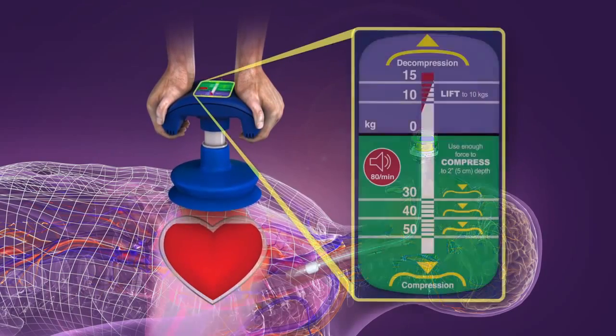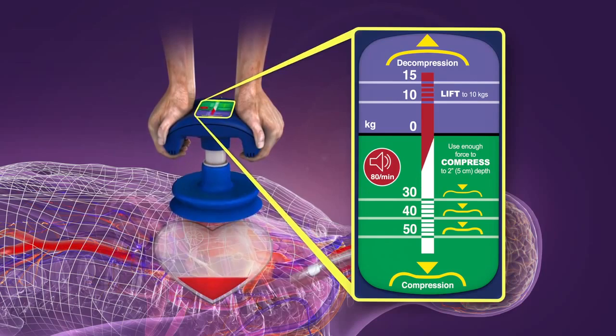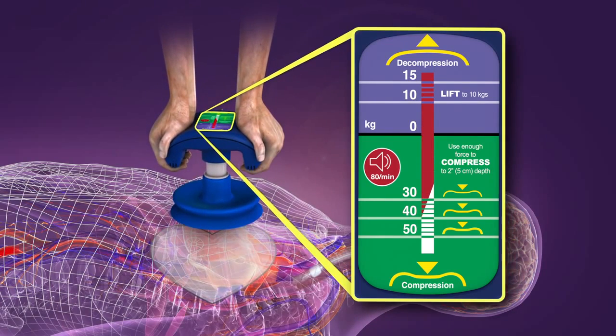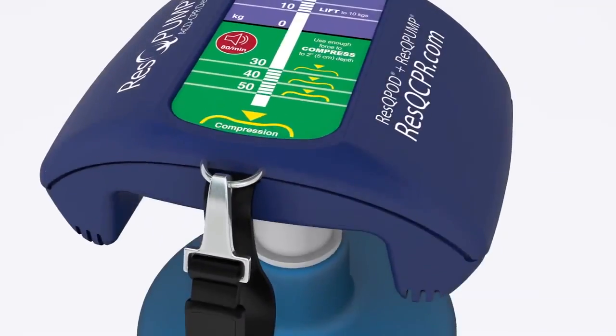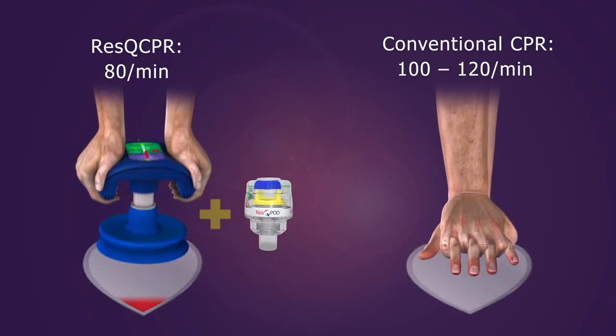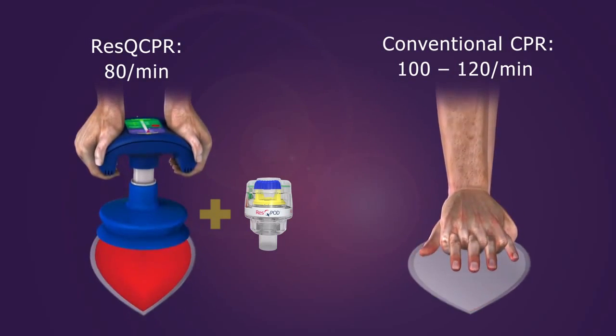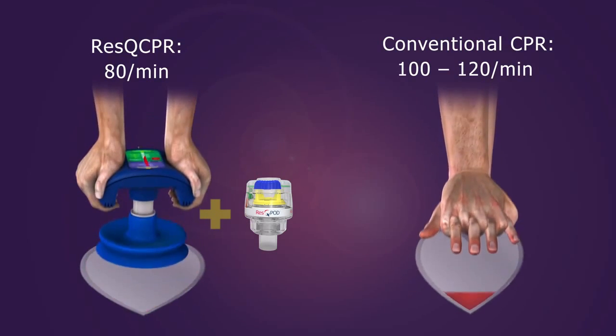A force gauge on the ACD CPR device is designed to guide both compression and lifting forces. A metronome tones at 80 per minute as a guide to the proper compression rate. ResQCPR is performed at a slightly slower rate than conventional CPR to give the heart more time to accommodate the improved preload and cardiac output.